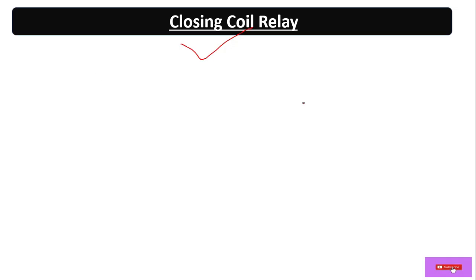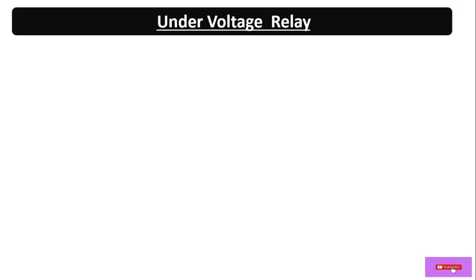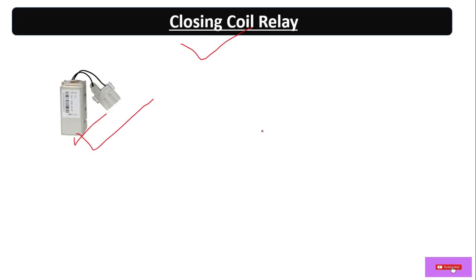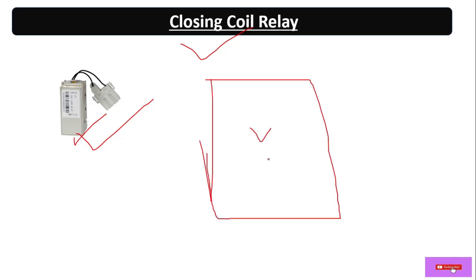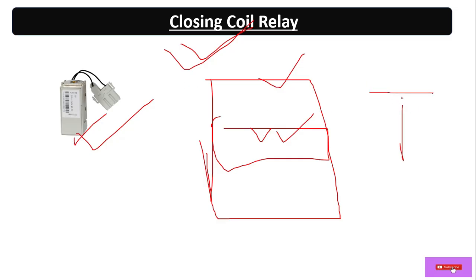We can also manually give the trip command through the TNC switch — Trip, Neutral, and Close. The closing coil looks similar to the shunt coil but has a plunger inside. When a fault is cleared and we want to switch the breaker back on, the closing coil helps to close or make the circuit, and it can also be operated manually through the TNC switch.